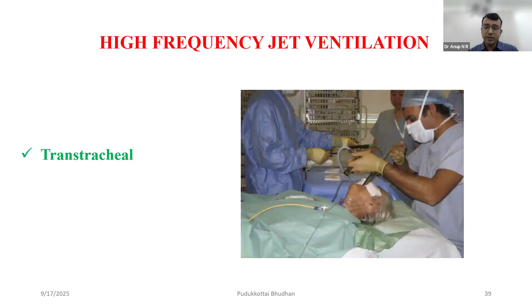A newer advancement in this field is the Ventrain, which is a single-use device where they provide you with the cannula and a hand-holding device, and the end is connected to an oxygen source. By releasing your fingers, you can ventilate the patient. One point which we need to remember here is the expiration is active here. The expiration is active, whereas in all other techniques, the expiration is passive. Here, the air is sucked out, again by the Venturi principle, inside the machine.